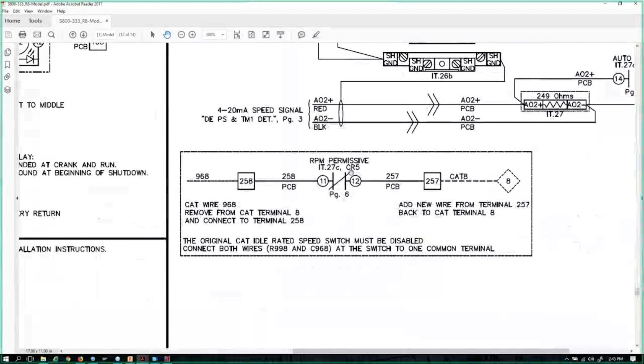I'm going to use the other set of contacts for that same relay that we just saw to control a ground into an engine input. Now what this does is, because this is a smart engine or an OEM engine control system with its own little computer, if this terminal in this case is the original Cat idle rated speed, and a Cat does some different things, but if I change the ground status on this, in this case if I remove the ground from terminal 8, the ECM no longer sees a ground on this circuit, it will go to what we call rated speed.